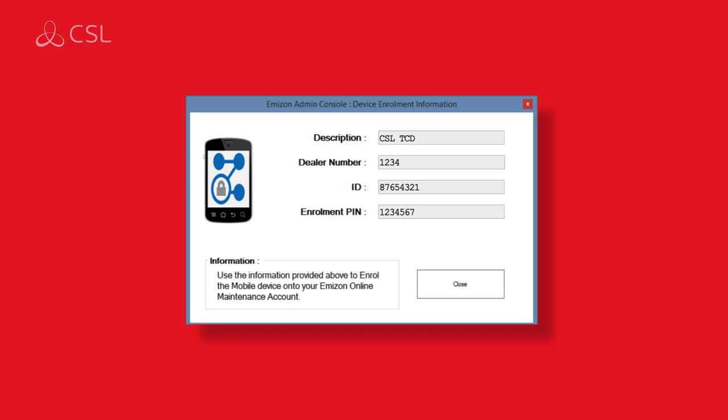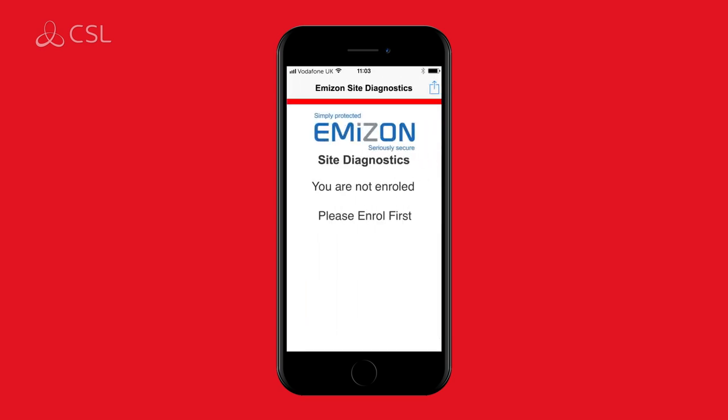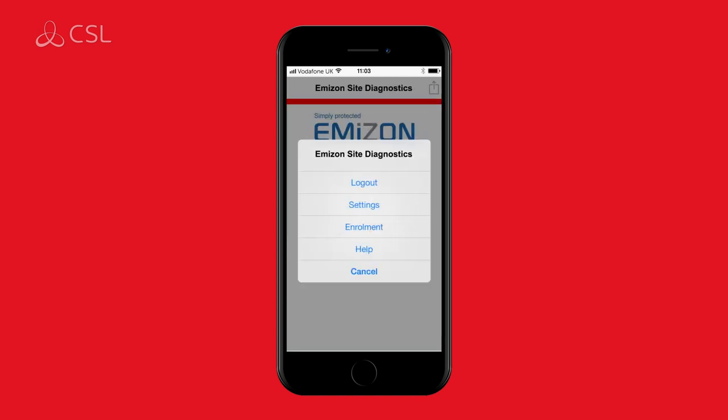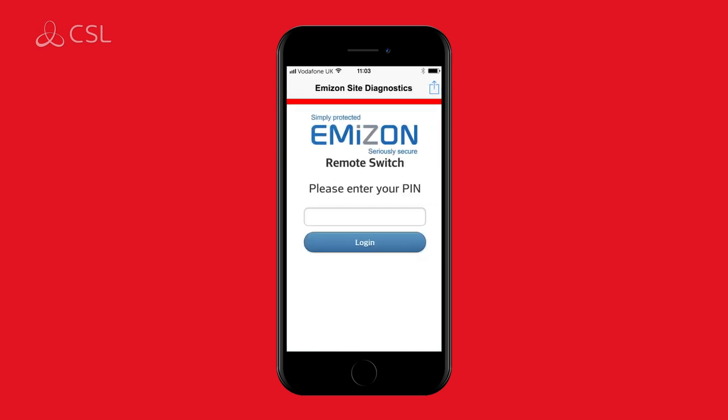A dialog box will open with enrollment details. To complete the enrollment process, download the Emizon Site Diagnostics app from your smart device's app store. When the app has been downloaded, you will be prompted to enter a pin. Click the icon in the top right hand of your device to enter the enrollment screen — this will appear as three dots on Android or a box and arrow icon on iOS devices. Select enrollment from the list of options to open the enrollment screen. Enter the details created on the admin console. The installer creates their own user pin, which they will use for future logins.